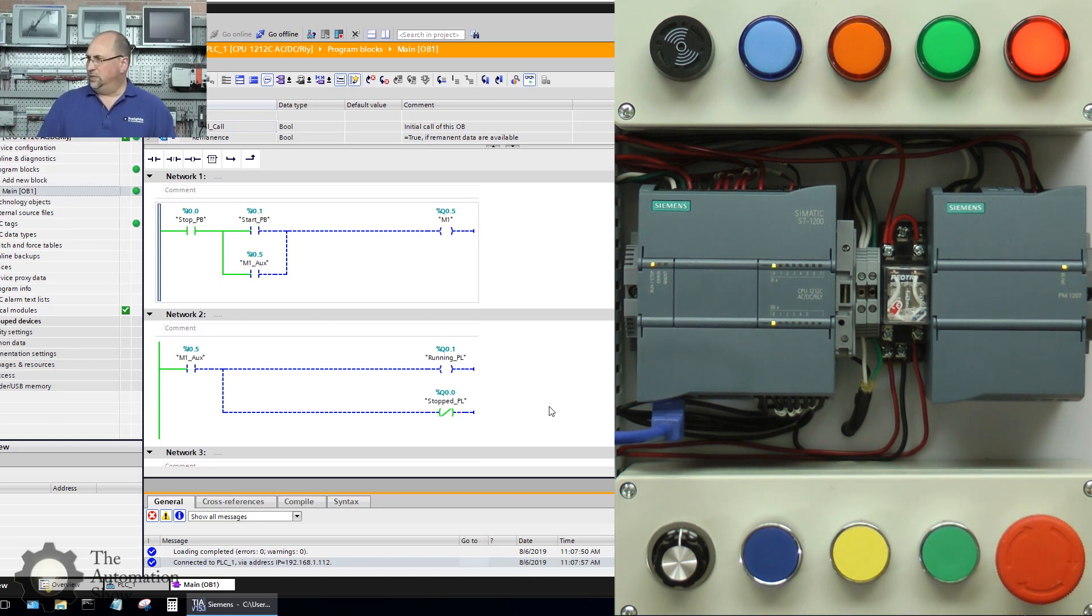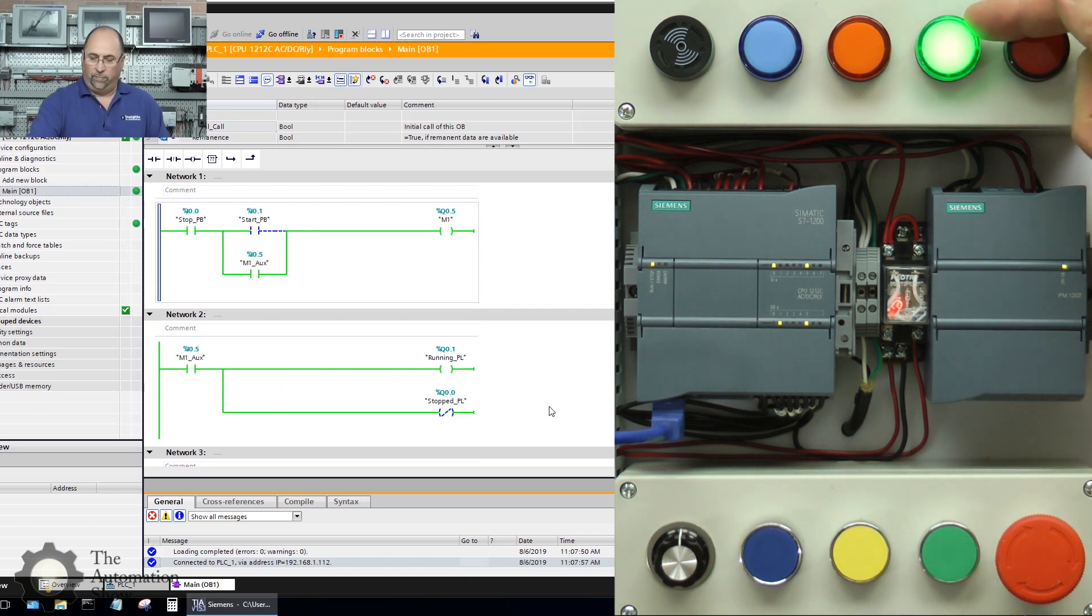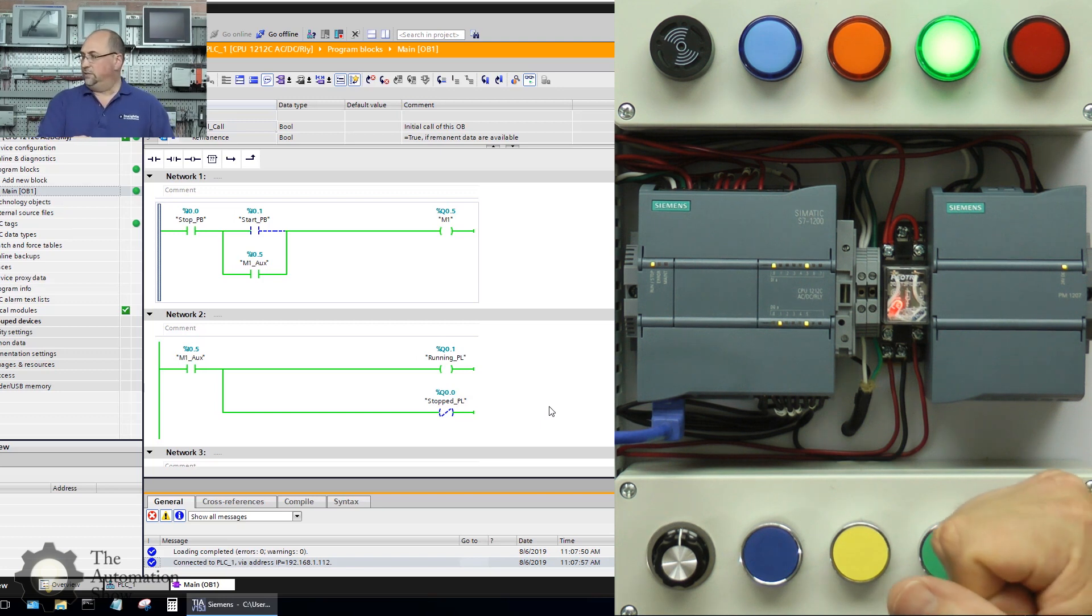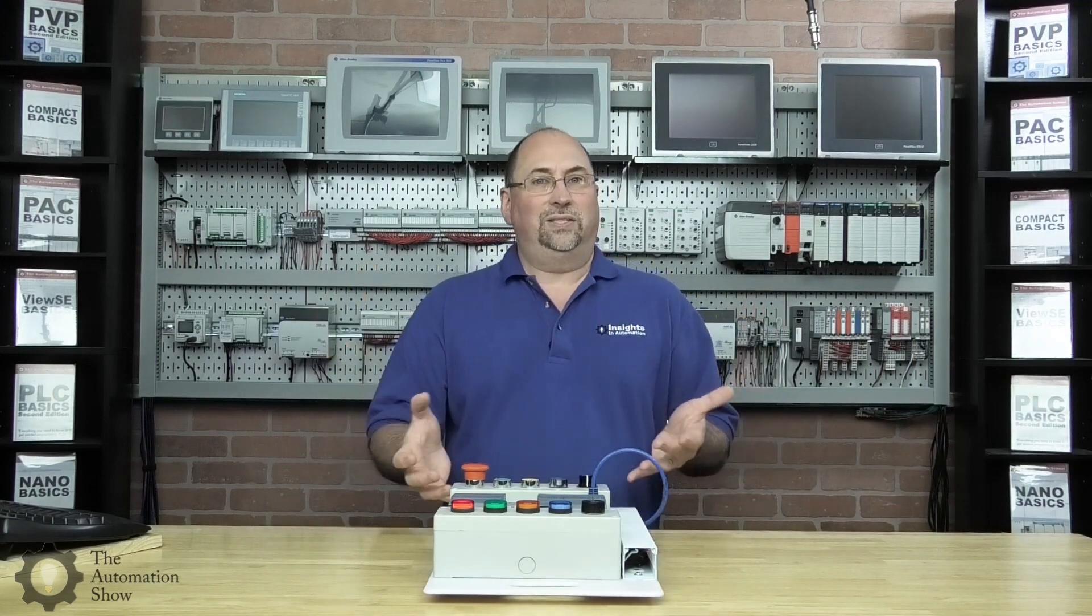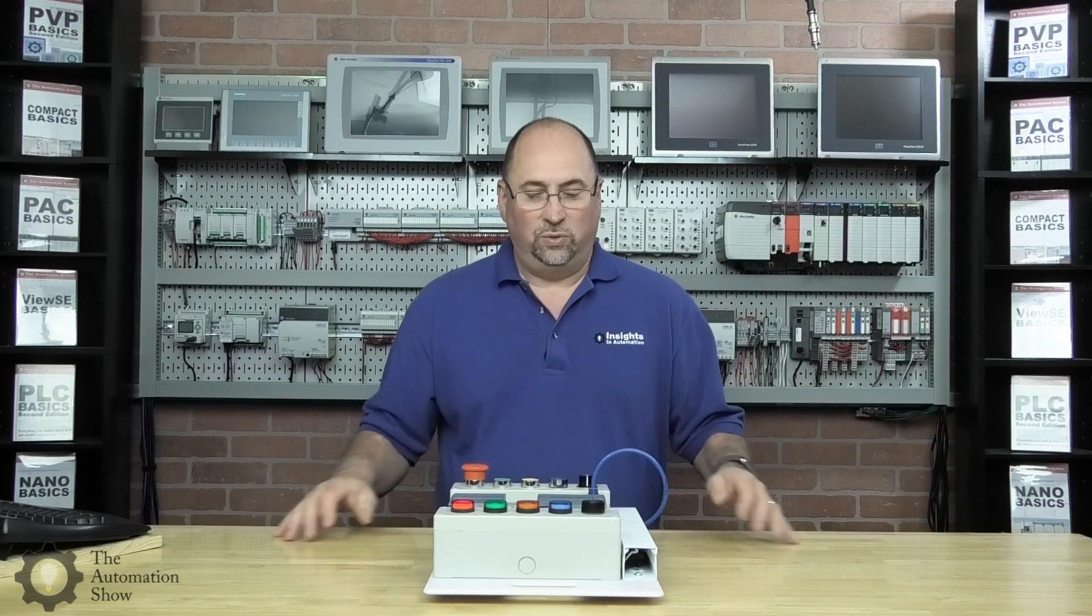Let me release my stop button, press my start button. And look, I have my green pilot light. My relay is on. You can see the auxiliary contact sealing in my start button, keeping everything on. And if I hit stop, see, I dropped it out again.